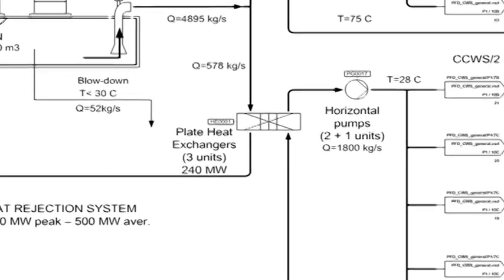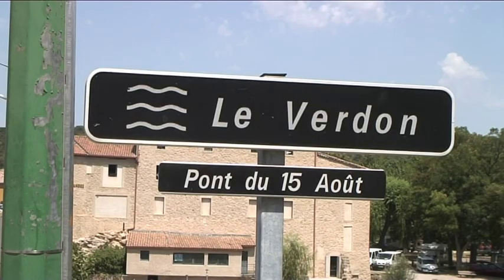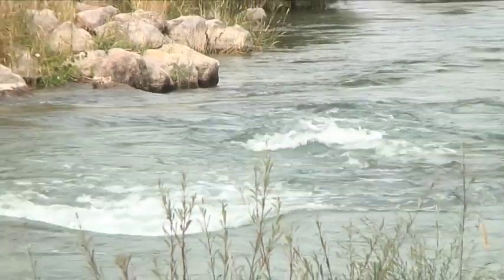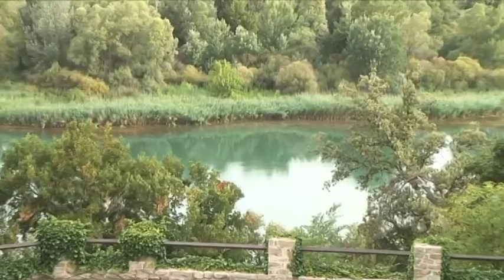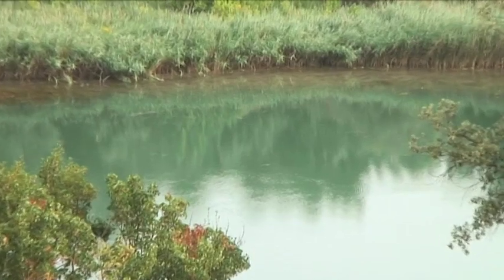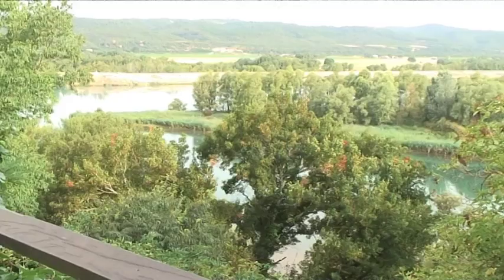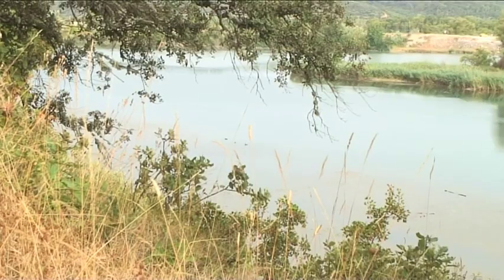The environment receives the heat through evaporation of the cooling water in the cooling tower basin. The ITER cooling towers are being designed to remove 1250 megawatts in thermal power. Compared to a nuclear power plant, this is about one third of what you might see at a nuclear power plant. The amount of water that ITER will use on an average basis is 3 million cubic meters per year.